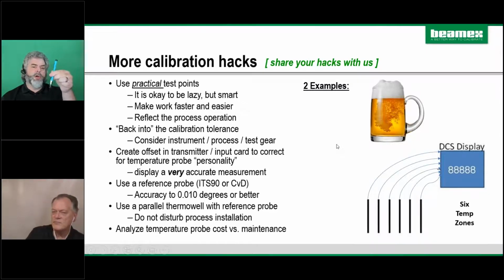So if temperature probe 1 measures 2 degrees low, they go to the DCS and put an offset of plus 2 to make it perfect? Exactly, they just did that on each of them. But it wouldn't be that bad.